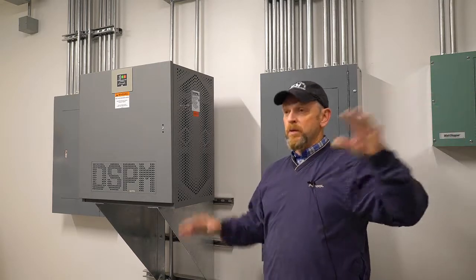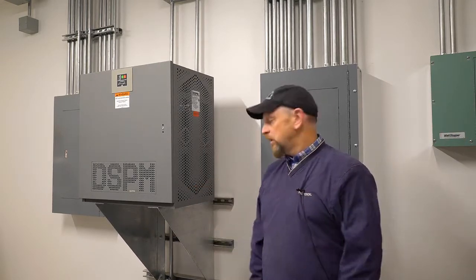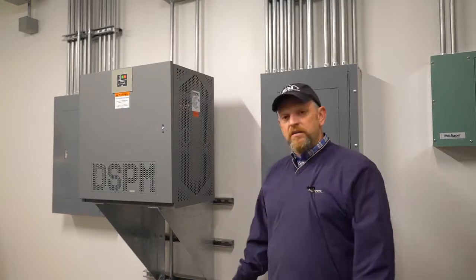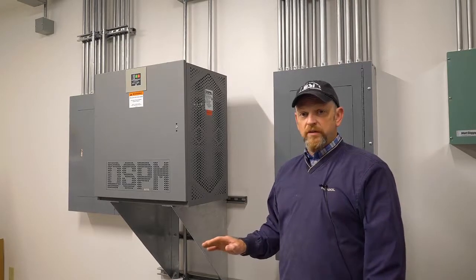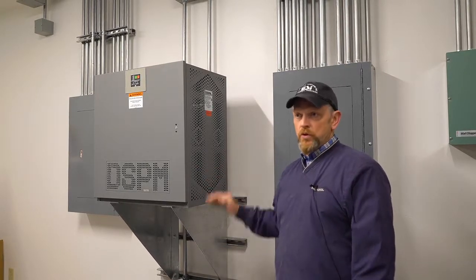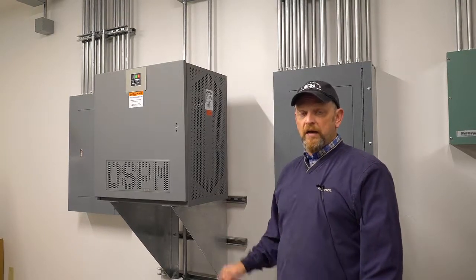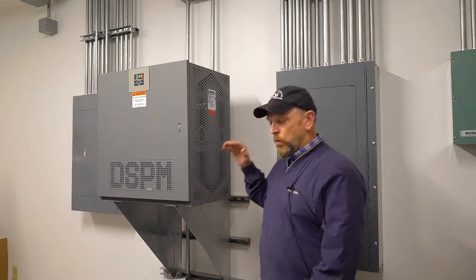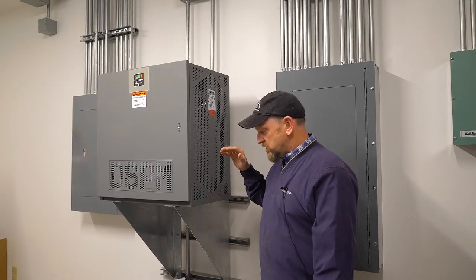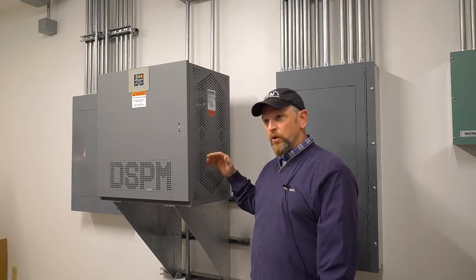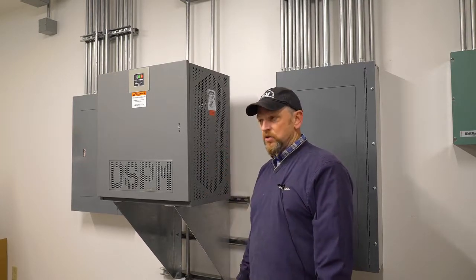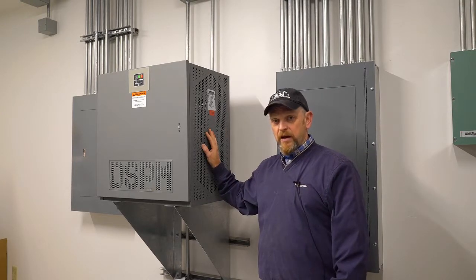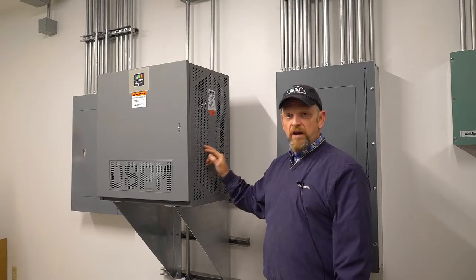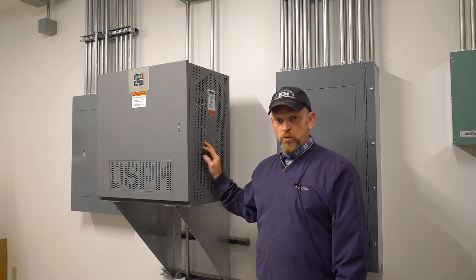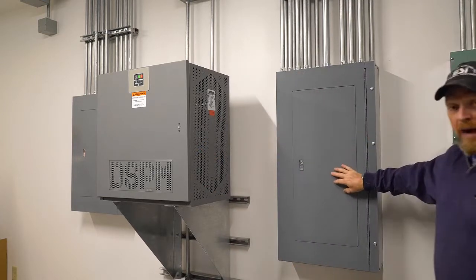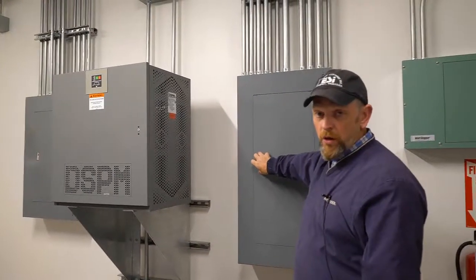The wing is separate. We're talking about the lobby. So there's some lights that you'll notice throughout the building that are on 24/7, and those lights are all controlled by these 2 inverters. We've split the power between outside and inside. Well, it's not quite that way. That sounded bad. Some of the circuits for outside go into one inverter, and then the rest of the circuits are all inside circuits. Once again, these have a 90-minute backup, and we'll have to figure something out if the power is out for more than 90 minutes. This is the regular power panel, or as the prints call it, the BA panel.